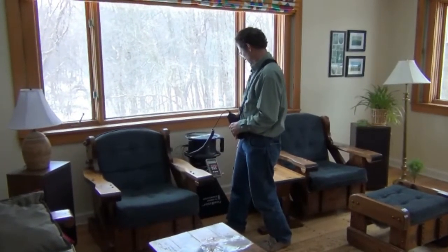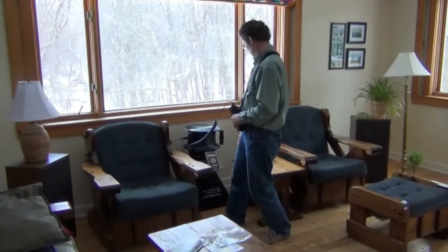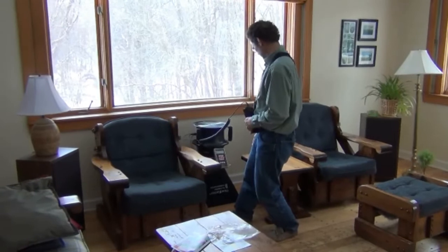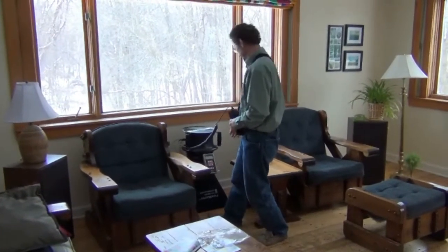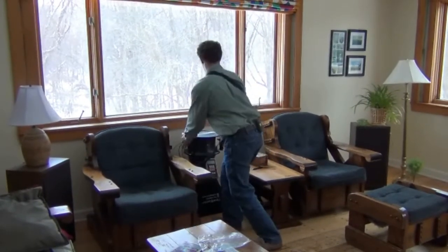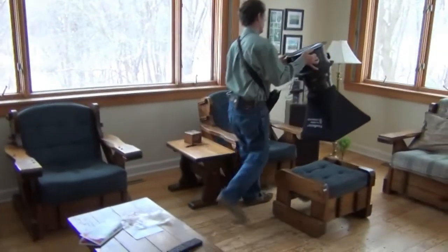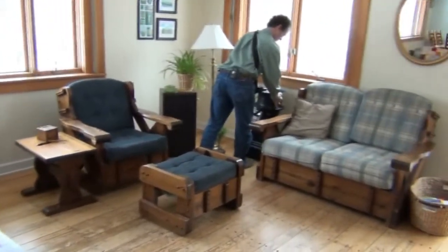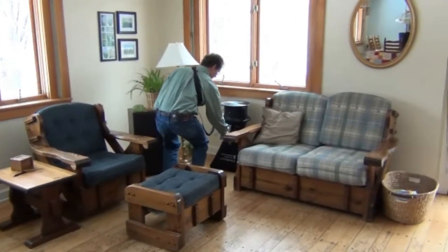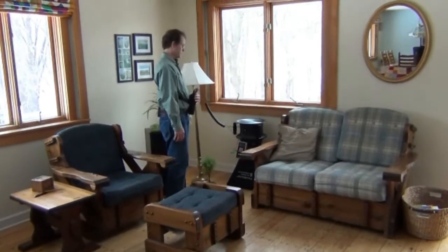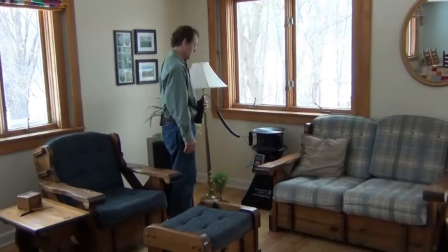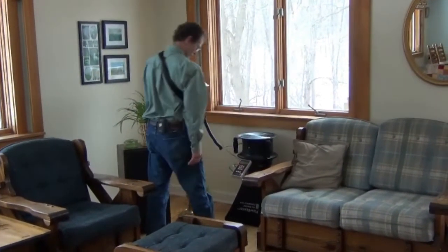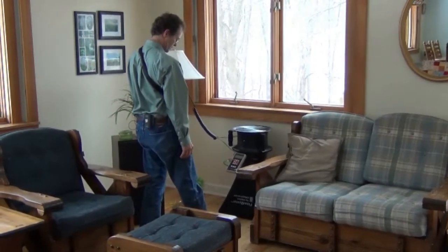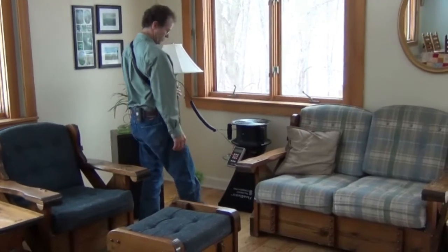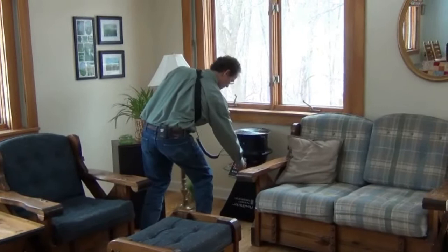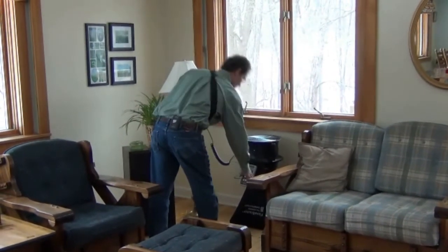Now watch this one ramp up. Watch your channel A as it gets closer to 0. And this one we're at about 63 CFM. Push stop fan. And we'll take one more measurement here. Start fan. So you can see it doesn't take long, we've just taken 4 measurements. And it goes pretty quickly once you have it set up. So this one we're reading 54 CFM. Hit stop fan. And I'll turn the gauge off now.